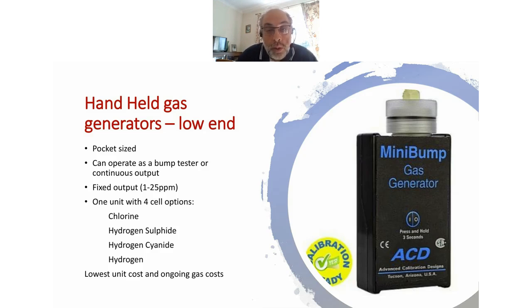So when you order the cell, all of our cells have a microchip in, which tells the instrument their characteristics and their lifetime of use. And you typically will specify between 1 and 25 ppm. And when you put that cell into the top of the instrument, into the screw area at the top, it will know what ppm it's going to be producing. This is an electrochemical generation, and has 4 options of chlorine, hydrogen sulfide, hydrogen cyanide, and hydrogen.